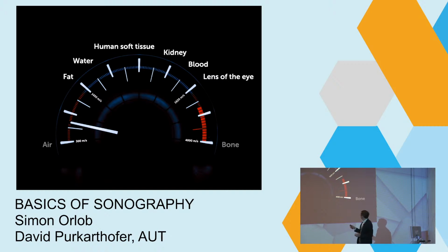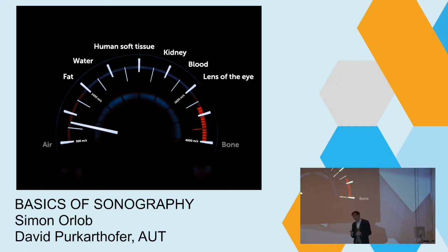And for all those things in the middle, like in the sweet spot, it's very easy for ultrasound to pass through. And if there's a reflection, it's not a 100% reflection. So at the border between fat and water, or water and soft tissue, some part of the ultrasound waves are reflected, but not all of it. If you hit either end of the spectrum, there's a total reflection. And that's something you have to keep in mind for using ultrasound, because you won't see anything behind an air-filled space, or behind solid structures like bone.